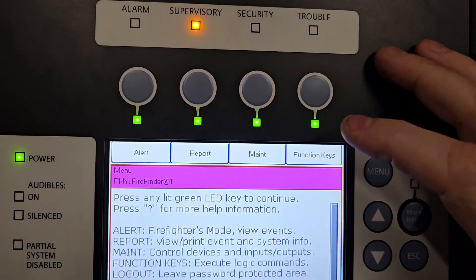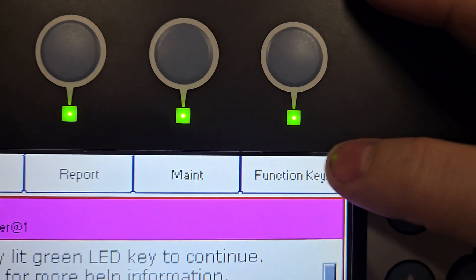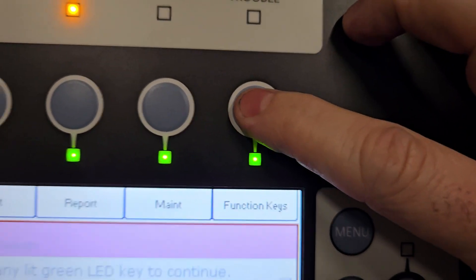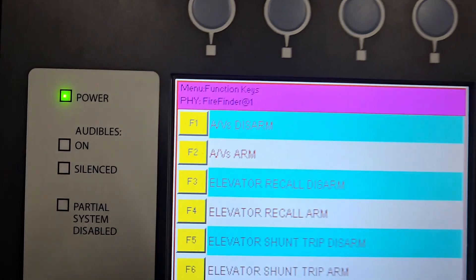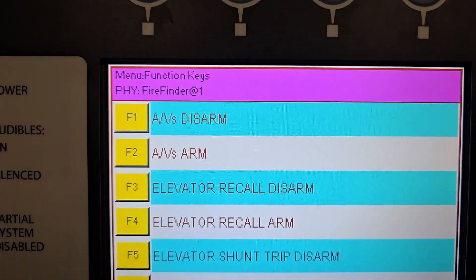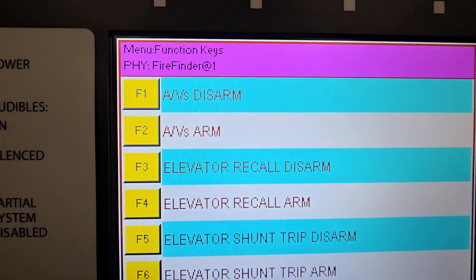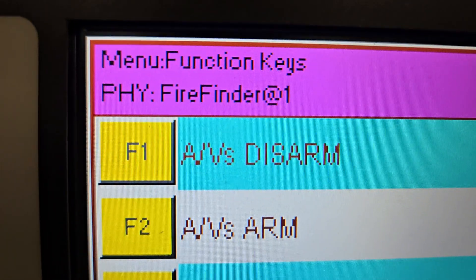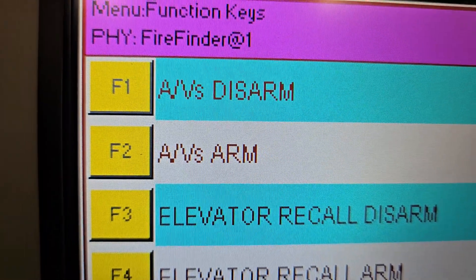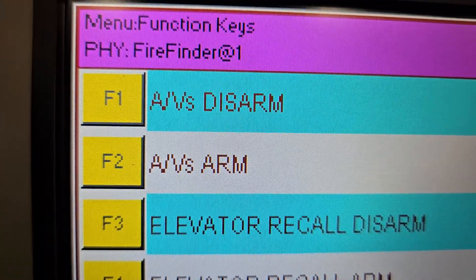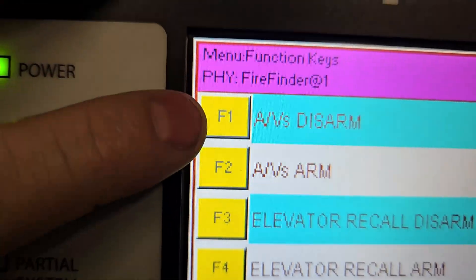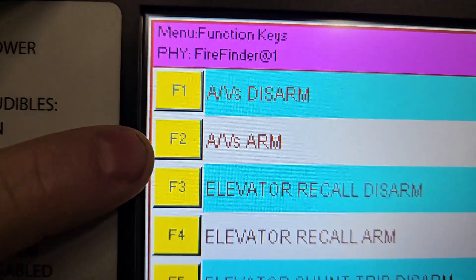For disabling, we're going to use the top right button, which is function keys, so we're going to hit this button. It's going to come up with a list of disable and enable points. We have F1 as AV disarm — audio-visual disarm — and F2 as audio-visual arm.